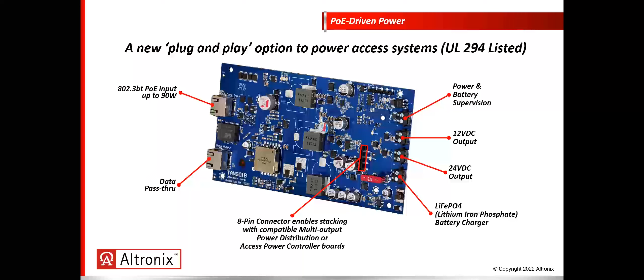I want to touch a little more on the LiFePO4, lithium iron phosphate battery charging. For those who don't know, there are a lot of advantages to lithium iron phosphate battery charging. You get a longer use life of battery—we can do up to 5,000 duty cycles versus 500 for a sealed lead acid battery. Depending on the manufacturer, it's anywhere between 2,500 and 5,000 duty cycles for a lithium iron phosphate battery, so the cost per cycle gets greatly reduced when you have that many cycles available.